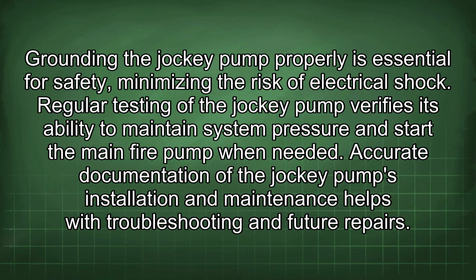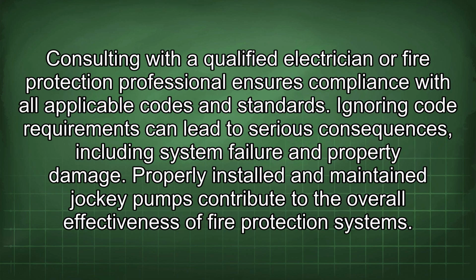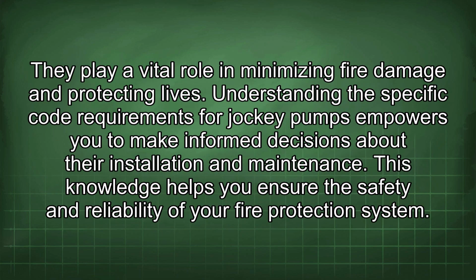Regular testing of the jockey pump verifies its ability to maintain system pressure and start the main fire pump when needed. Accurate documentation of the jockey pump's installation and maintenance helps with troubleshooting and future repairs. Consulting with a qualified electrician or fire protection professional ensures compliance with all applicable codes and standards. Ignoring code requirements can lead to serious consequences, including system failure and property damage. Properly installed and maintained jockey pumps contribute to the overall effectiveness of fire protection systems. They play a vital role in minimizing fire damage and protecting lives.